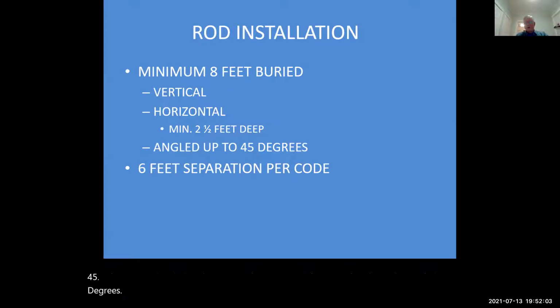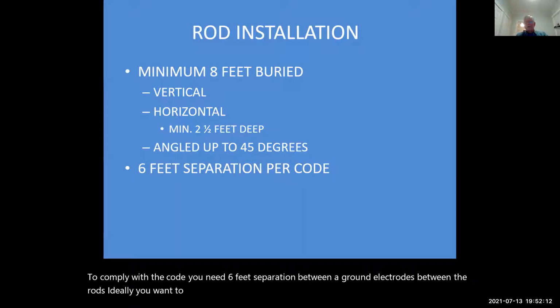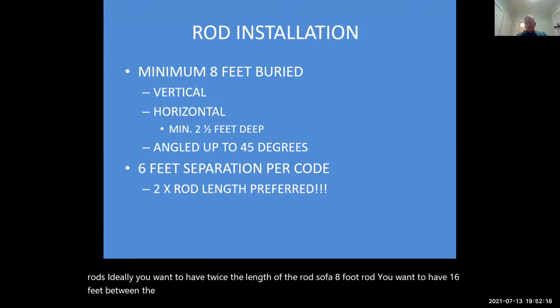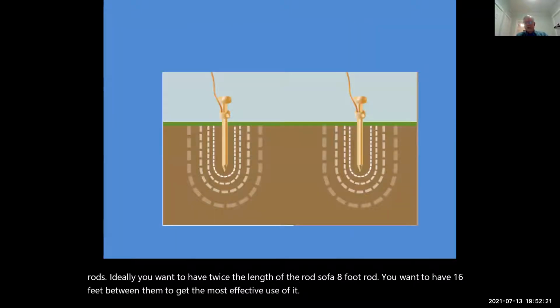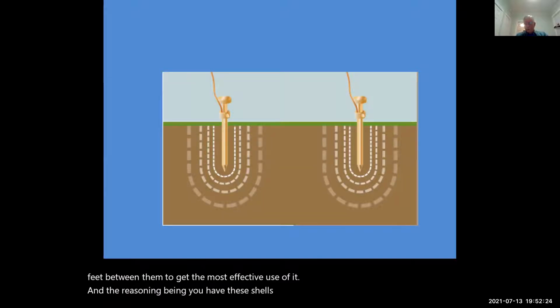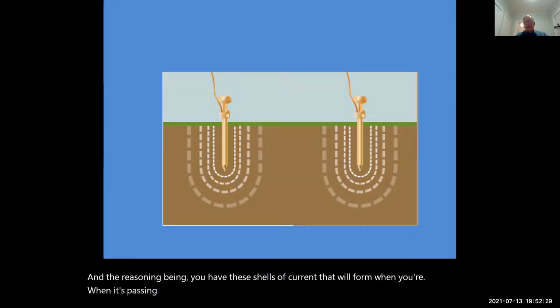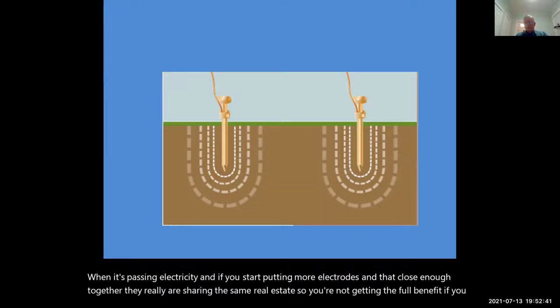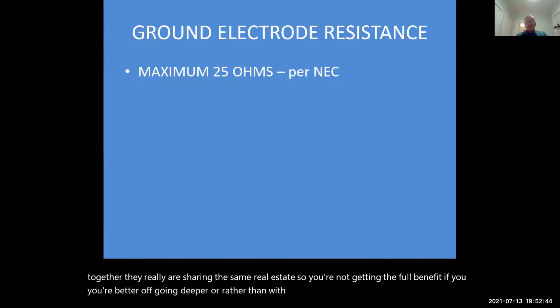To comply with the code, you need 6 feet separation between ground electrodes, between the rods. Ideally, you want to have twice the length of the rod. So for 8-foot rods, you want to have 16 feet between them to get the most effective use of it. And the reasoning being, you have these shells of current that will form when it's passing electricity. And if you start putting more electrodes and they're close enough together, they really are sharing the same real estate. So you're not getting the full benefit. You're better off going deeper rather than with more closely spaced.